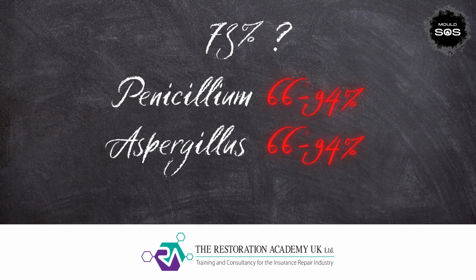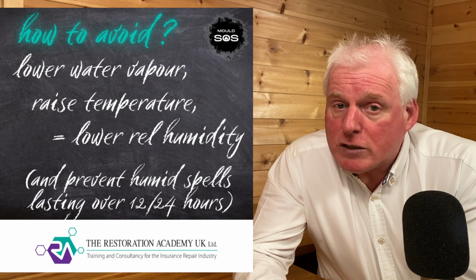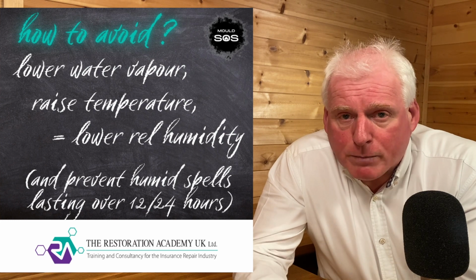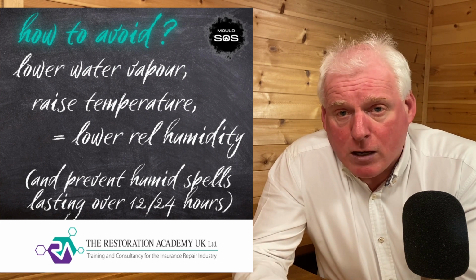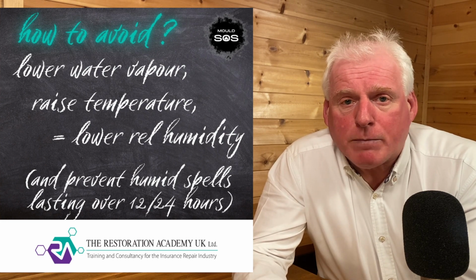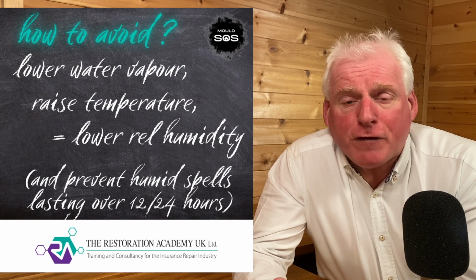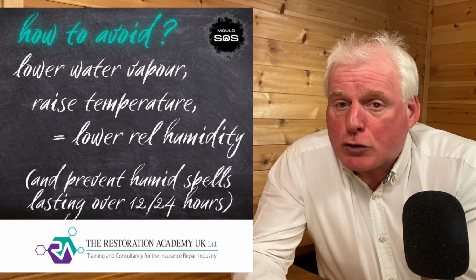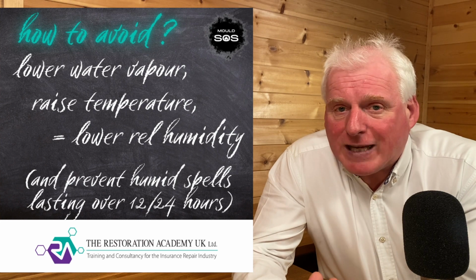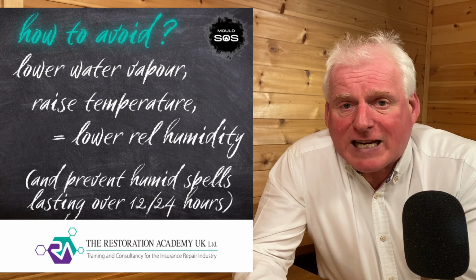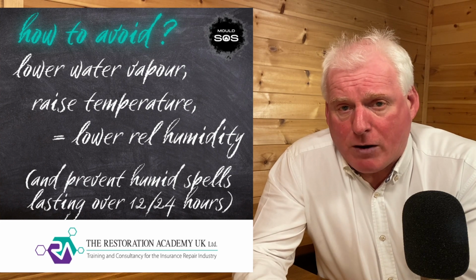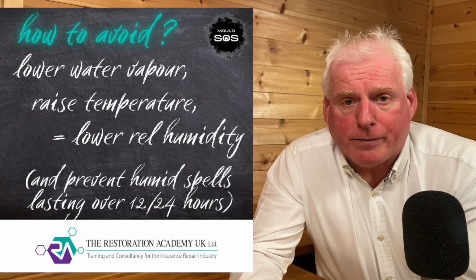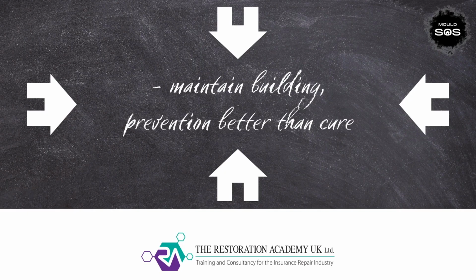How do we avoid this? We have another video that goes into a bit more practical detail, but in principle we have to reduce the amount of water in the air. We have to make sure that the heating system is adequate and warms the wall sufficiently so as to avoid not just the dew point or condensation, but also to keep it away from a humidity level of more than 65% for any extended period. Or we need to do both. We should also manage and maintain our buildings to ensure that we do not allow water to penetrate the building envelope, as we discussed in video 2.